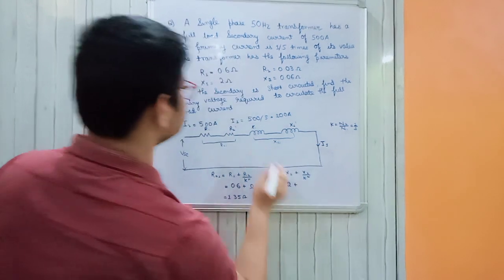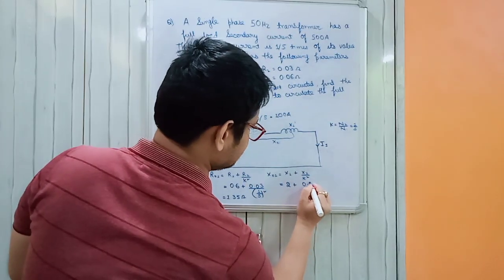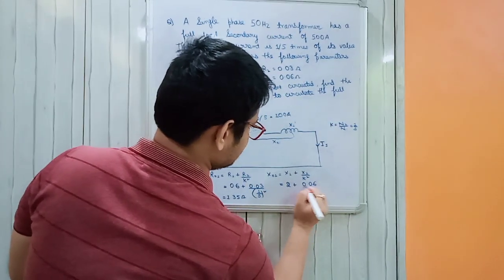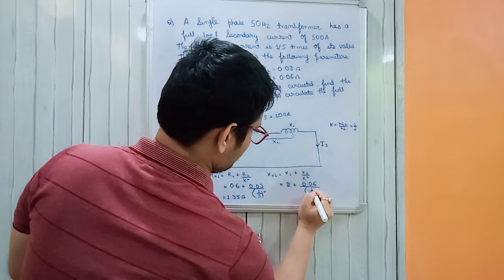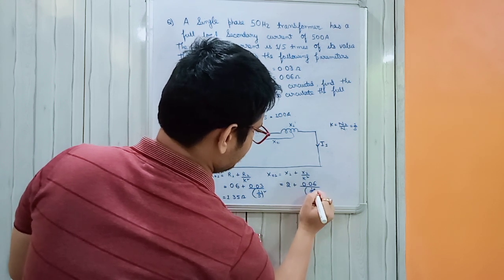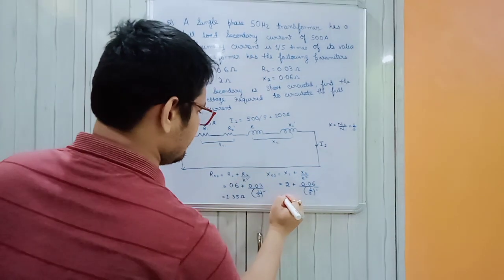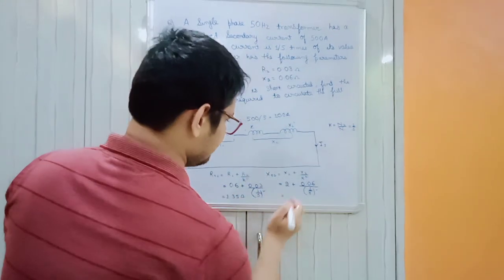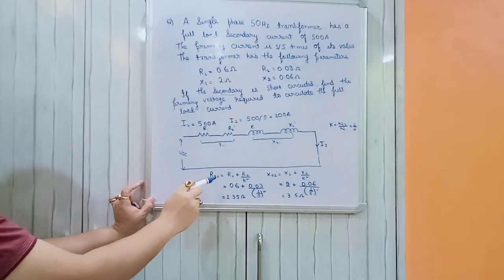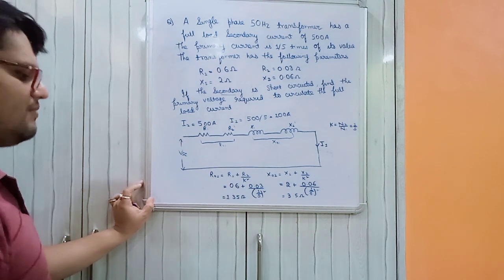For the reactance: X01 = X1 + X2/K² = 2 + 0.06/(1/5)² = 2 + 1.5, which gives X01 = 3.5 ohm.